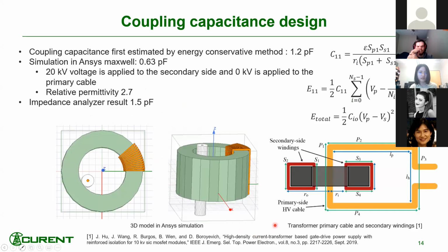And also the coupling capacitance design. Basically on the right it shows how you can calculate the capacitance based on the length and the distance of the windings. A second approach is to simulate in ANSYS Maxwell. You can just assign a voltage like 20 kV on the secondary windings and 0 kV at the primary cable to see the capacitance between them. What's essential in the simulation is to set the material relative permittivity, the material characteristics, the same as the potting material that you've chosen. You can do the calculation and simulation, and you can also directly measure it using an impedance analyzer.